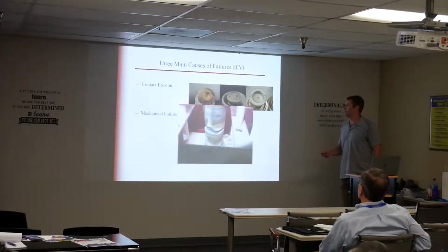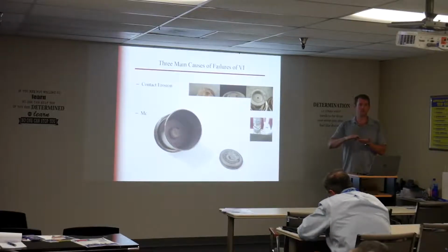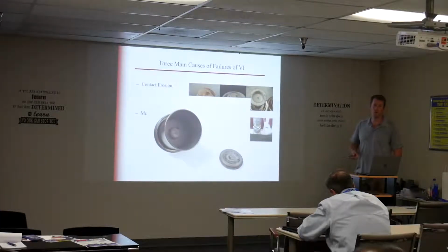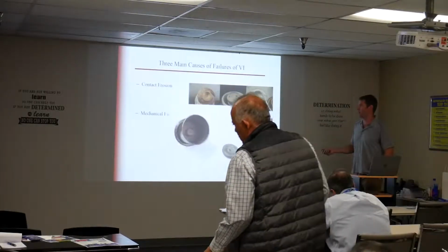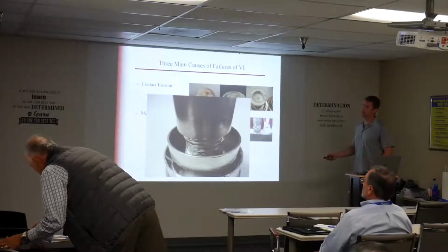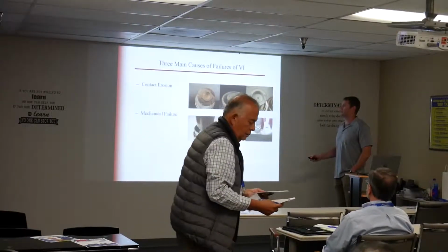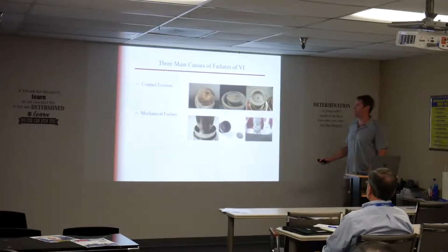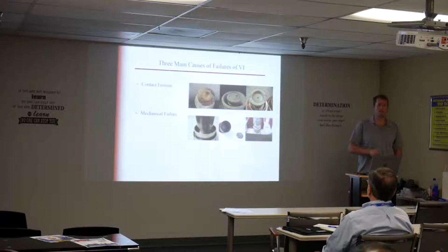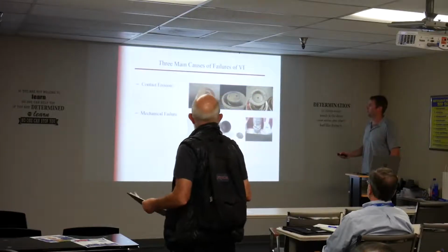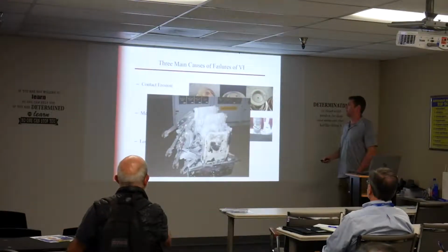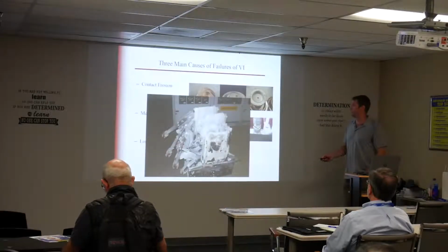Number 2 is mechanical failure. Like I said, these interrupters are only opening and closing 10 millimeters, as opposed to the old air breakers, it's 6 to 8 inches. So mechanically, these are rated for tens of thousands of operations, but just like everything, it has a mechanical life, and eventually different welds, seals start to degrade. This is also a visual check, because breakers have operation counters. Typically, I start seeing after 3,000 operations is when you start having issues with the breaker mechanism, and then the breaker's not opening and closing as fast, and you start seeing issues with the bottle. So 3,000 operations.